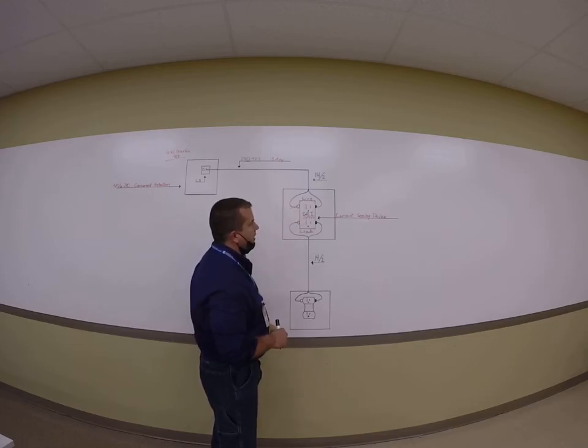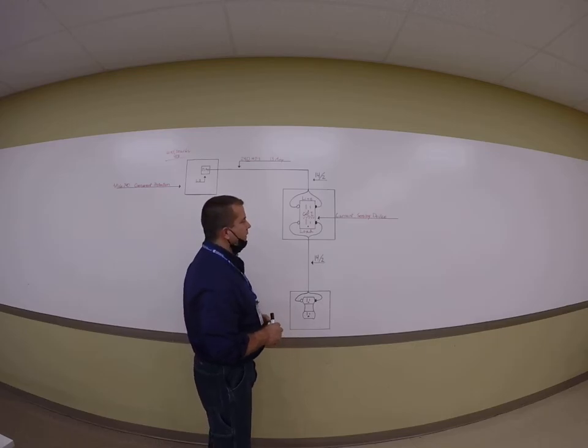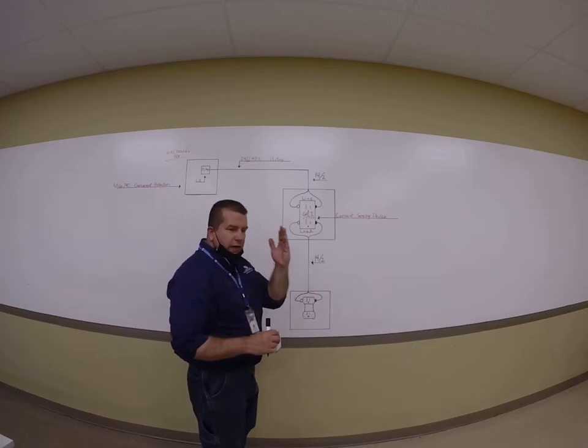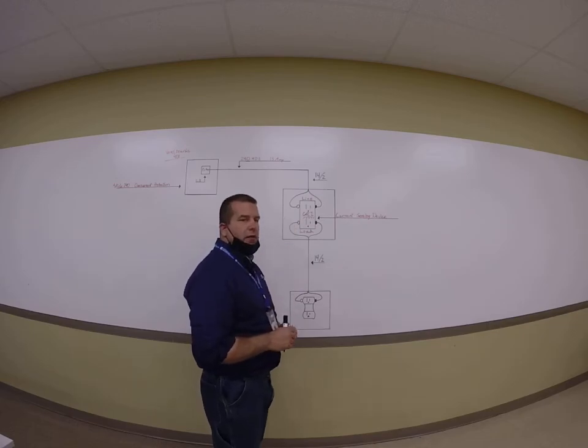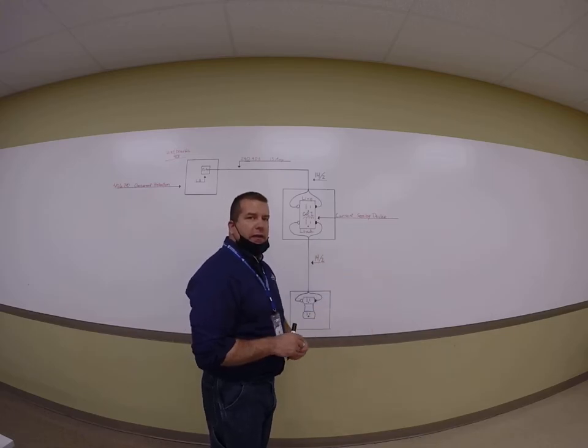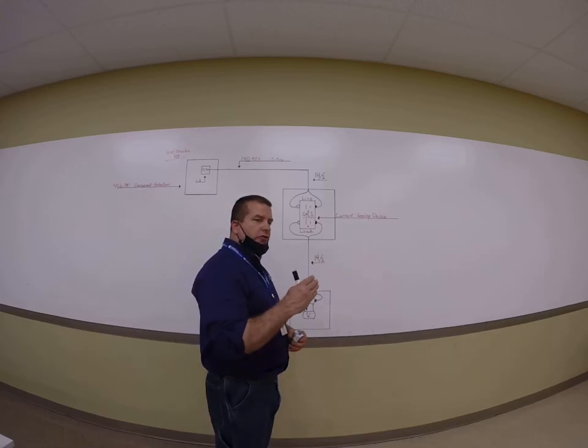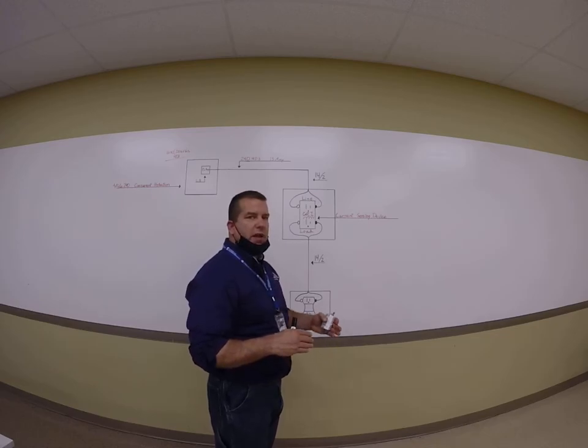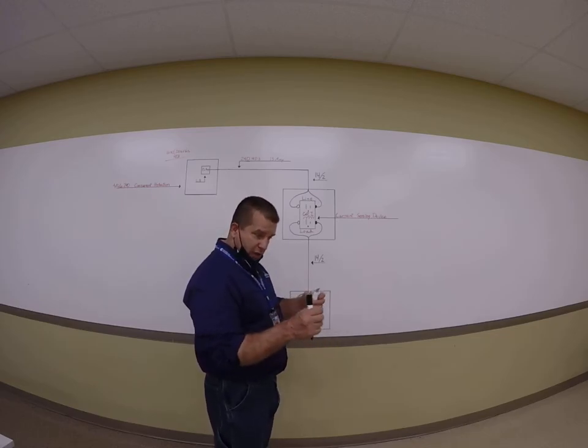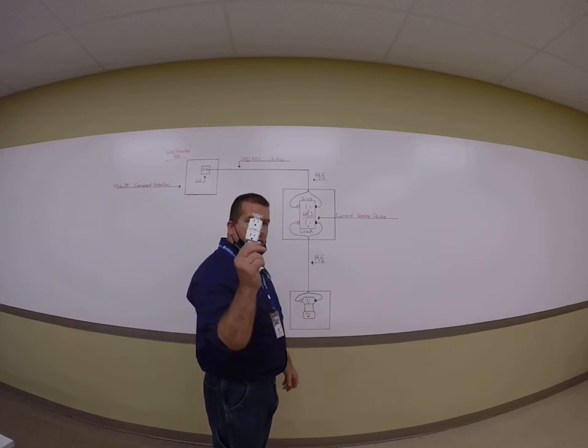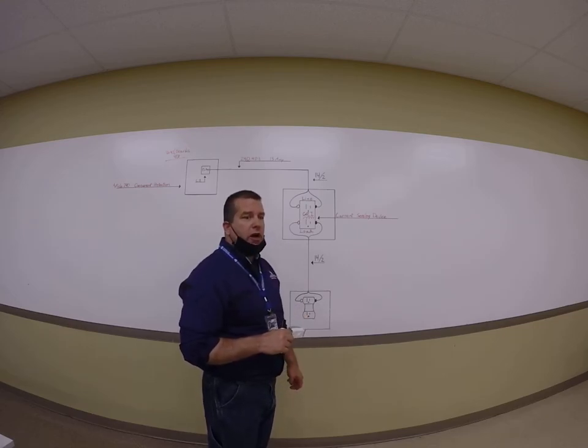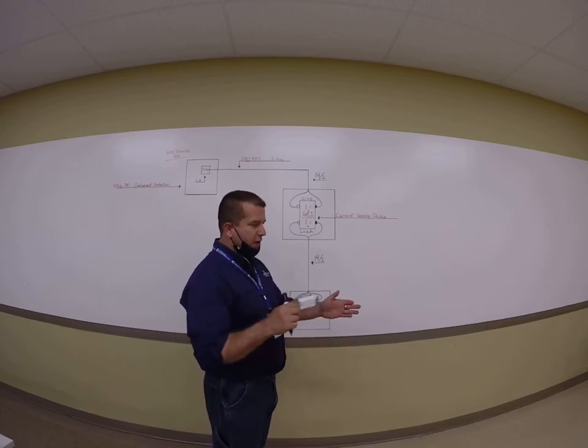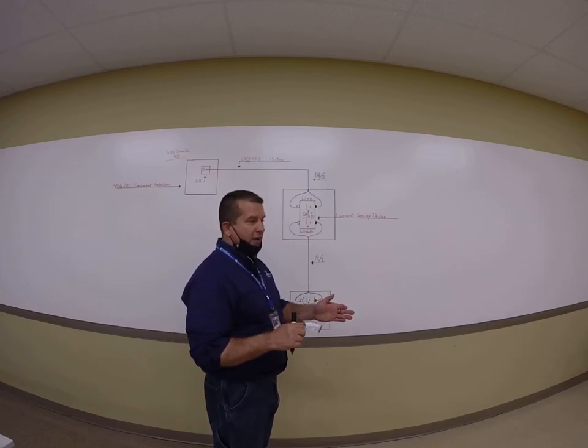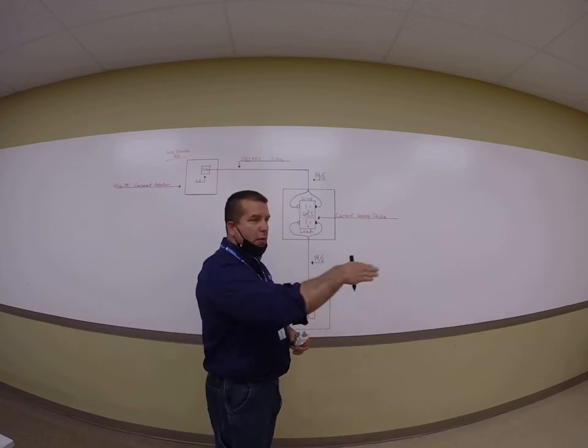And there's a current sensing device for simplicity that's measuring what's leaving and what's coming back. So in my other video, I just gave the hypothetical example. If I have 5 amps that leave, the neutral has to return with 5 amps. If there's a 4 to 6 to 8 milliamp difference in that current coming back, it's going to allow this to open the circuit. And we talked about that as being leakage current. So if 5 goes out and 5 doesn't come back, if 4.5 came back, then half of a current is somewhere else in the circuit.